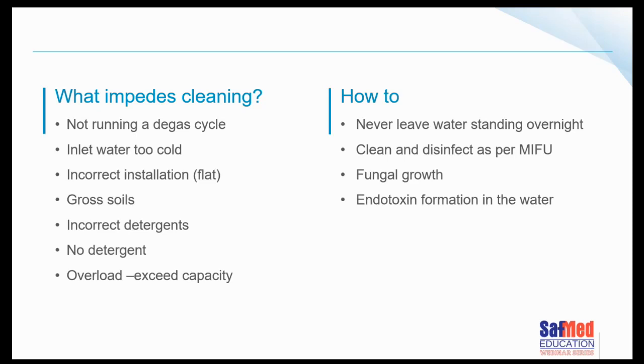As I said, never leave the water standing overnight, please. At the end of the day, if you're going to use the machine and you're going to continuously work with it overnight, that's great. But somewhere along the line, you need to let the water out. You need to follow the cleaning instructions, as it said daily, drying off the lid, drying off everything above the waterline. The cleaning and disinfection cycle, you need to run it once a week. Why? We don't want fungal growth and we don't want endotoxin formation in the water.